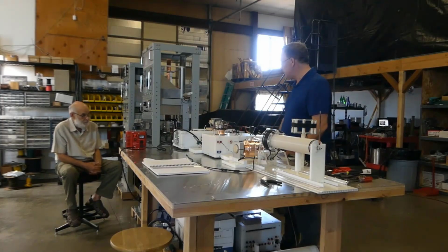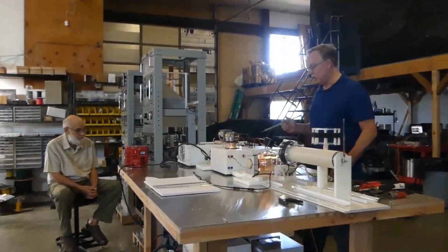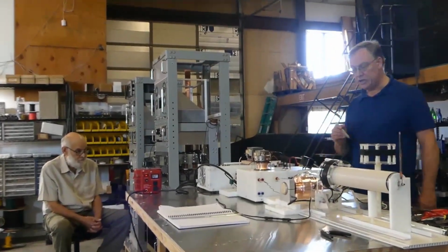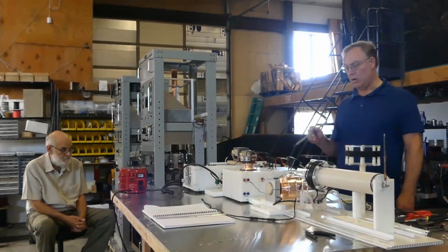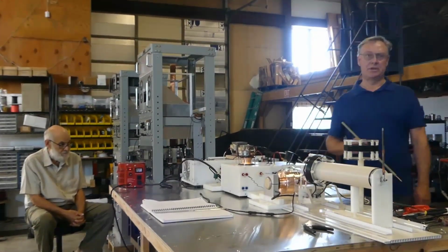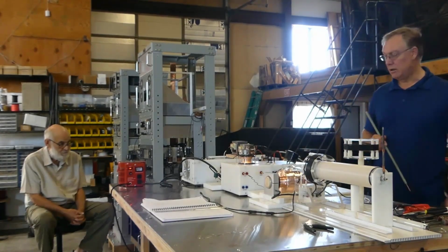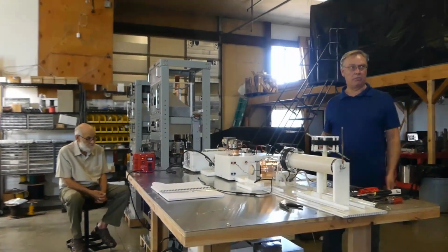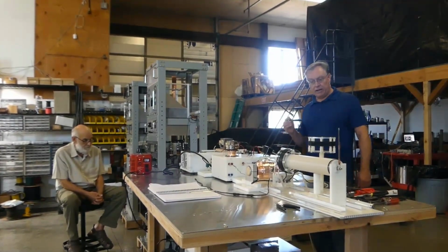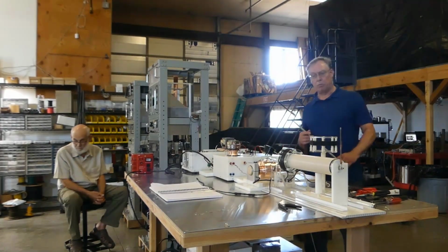What about 100 milliamps? I would say that's their extreme. So we are carefully adjusting the system to keep our plate current under 500 milliamps and our grid current under 100 milliamps. That keeps the tube in the center of its characteristics, particularly as we have a lower airflow right here.